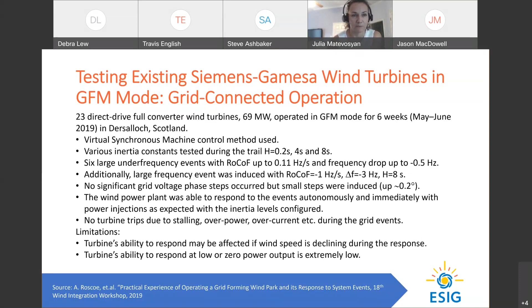One more thing that they suggested to overcome this limitation is that the inertia constant can be configured, can be changed in real time based on actual wind conditions. So during lower wind conditions, a less aggressive inertia constant can be used. This is challenging from a system operator point of view because you have a changing inertia constant in real time, but this is a flexibility that is not there with, say, synchronous machines or synchronous condensers. Next slide, please. Now I'm ready.